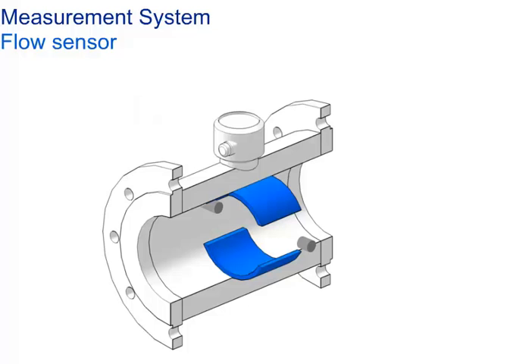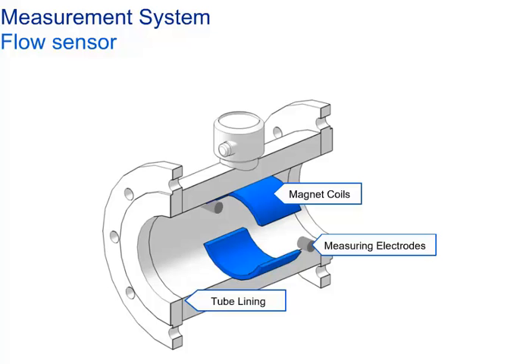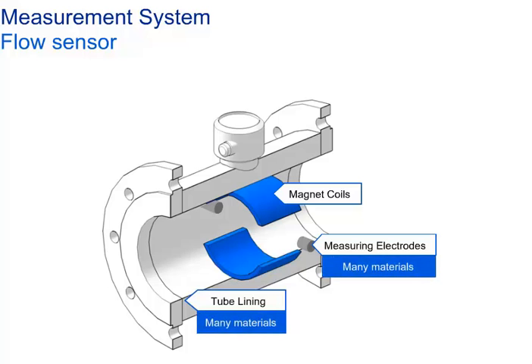Let's take a closer look at the flow sensor. It consists mainly of magnet coils — the coils and surrounding structure are designed to produce a consistent magnetic field across the whole pipe area — and measuring electrodes to pick up induced voltage. An electrically insulating tube lining is required to preserve the signal voltage and allow it to be transferred to the electrodes. The tube lining and the electrodes are wetted parts in direct contact with the fluid, so proper material selection for corrosion resistance and potable water approvals is vital.